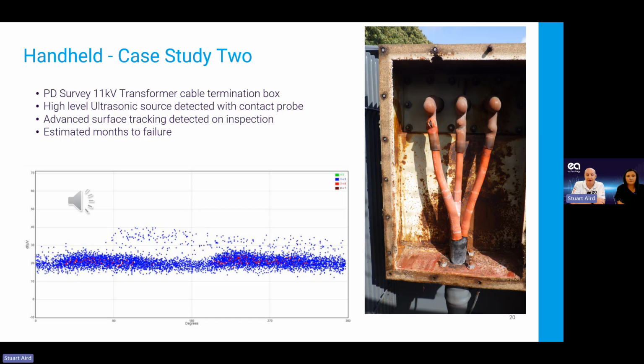So we've applied the contact probe. The sound is not quite as distinctive, but we did manage to pick it up. We can see it's quite advanced by that point. Also, there's things like the Ultra Bolt that we've recently released, which we could fit into things like cable termination boxes where there isn't an air vent, and it gives you a much better path inside that cable termination box as well. But again, we've managed to pick it up. We've prevented the failure, but again, it's quite close to failure by the time we've picked that up with our annual surveys.